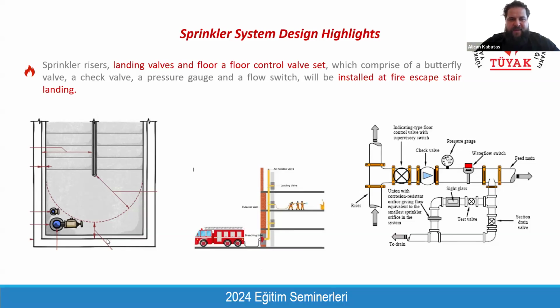But this equipment and also the landing valve should be located within the fire escape stair. The main reason is that the fire escape stair is considered a safe place, and in case of any fire, you can reach the fire escape stair without having any risk. That's why all of these fire safety related equipment are required to be located within the stair landing. Also, when the fire brigade comes into the building, they will use these landing valves to take water and interfere with the fire. Therefore, in order to have a safe preparation, they prepare themselves within the landing of the stair, and the landing valve is found within the staircase, so that they prepare their hoses, attach their hoses to the landing valve and go into the floor to interfere with the fire.